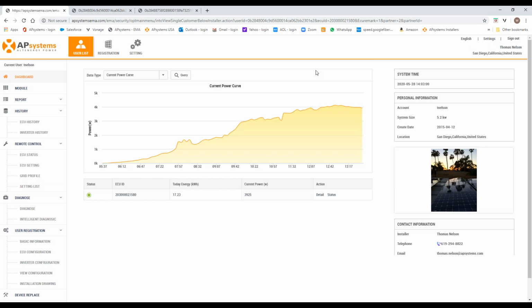We are, as Chris said, running up against the clock, but the quick question here is from an installer who's having some issues with YC600 tripping arc fault breakers, and their question is, what would be a quicker solution than replacing the older YC600 with newer ones with the ZigBee communication? I think I could be wrong, but I'm actually talking with a customer right now in Canada about that. But I think it was the 500s that were installed, not the 600s.